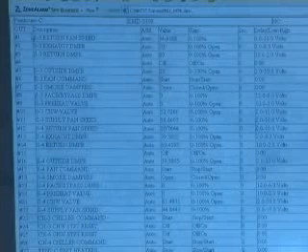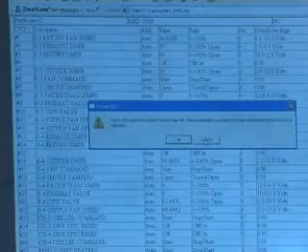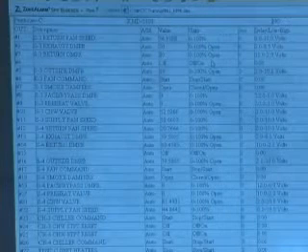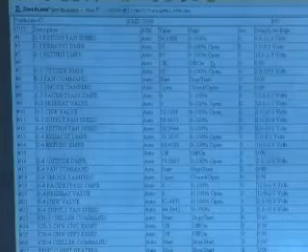This right here, this first group is outputs. These are physical outputs that are wired to the controller. So we have a VFD, an exhaust damper command. These are analog outputs. They'll start off being analog, 0 to 10 volt output, and this is just a software label here. So when our programmer gets on site and takes a controller from scratch, when we turn on a site, this is all blank. There's nothing here. We actually type all the stuff in, or copy and paste, whatever the case may be.